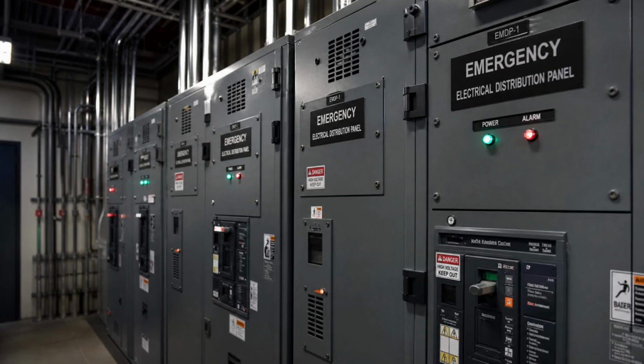Is there any corrosion on the electrical connections, the terminals of the battery, the connections at the control panel, the lugs where the output cables attach to the generator's circuit breaker? Is the exhaust system intact? The insulation on the exhaust piping undamaged, the rain cap on the exterior exhaust outlet in its correct position?